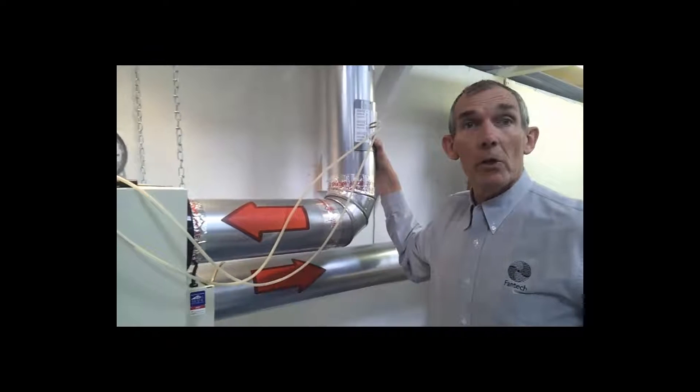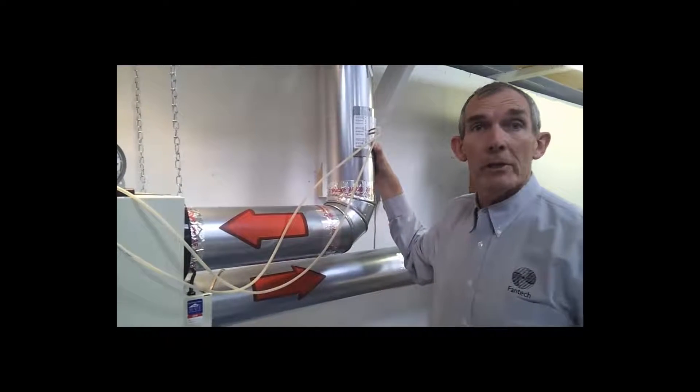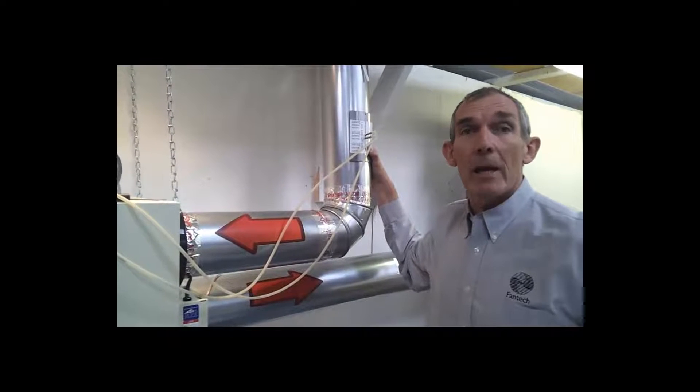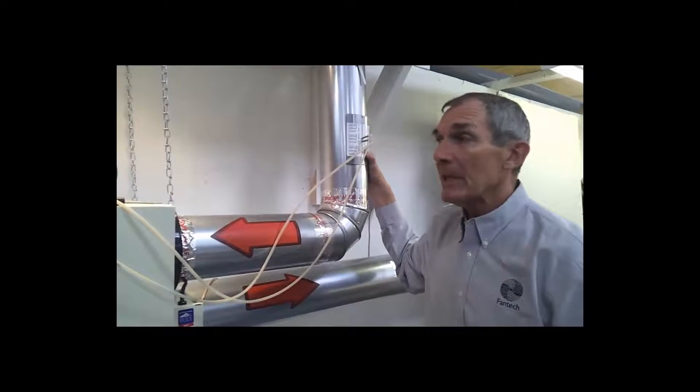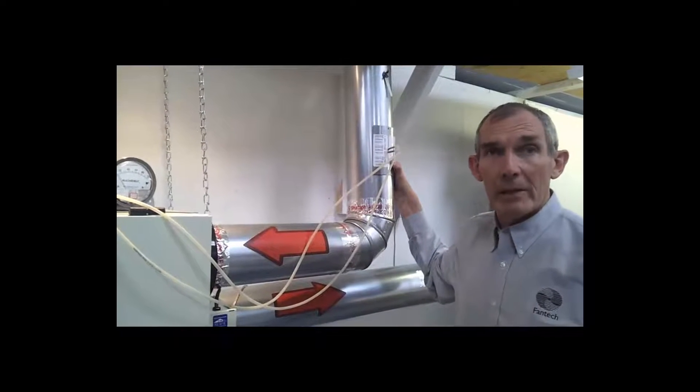A HRV or ERV system is deemed balanced if the supply and the return are within 10% of each other. In this case, they are out of balance, so they have to be balanced.